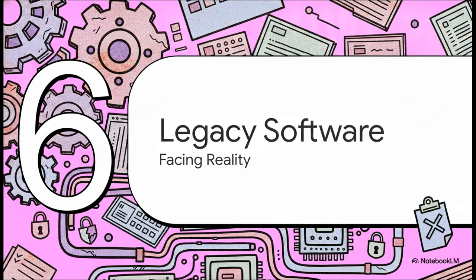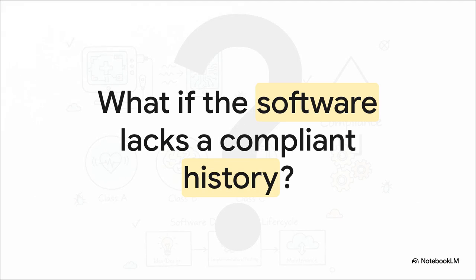Facing reality. Let's talk about facing reality with code that was written way before anyone worried about these strict rules. Maybe you acquire a startup, or you suddenly realize your existing product is actually classified as a medical device. What happens if that software is already out on the market, working just fine, but has absolutely zero compliant lifecycle history? Look, the temptation to just invent past design records and backdate them is strong, but let me be crystal clear, that is falsification of records. It's a massive regulatory offense.